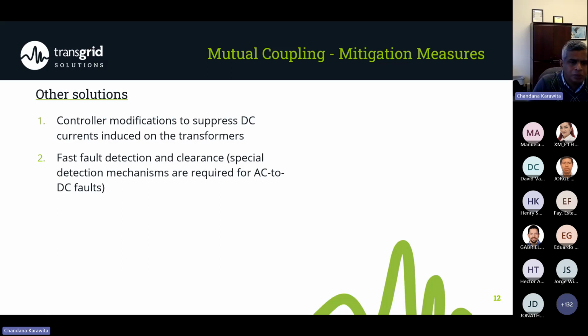The other possible solutions, especially if you see a significant DC current going into the converter transformers, is that we can add special controllers to suppress this transformer DC current. Basically, you have to add a parallel controller to the current control of the HVDC system, and that can suppress the DC current. And then another requirement, especially for the AC to DC faults and the transient over voltages, is that we need fast fault detection logic and clearing mechanisms.